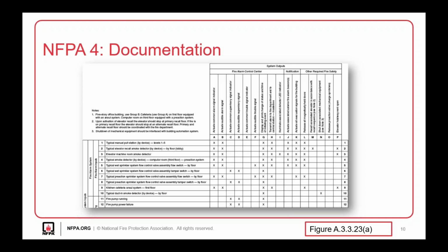So when performing the integrated test, it's important to document how each part of the input-output matrix was tested. This can be done in the form of a sequence of operation. The sequence of operation shows each input and then lists the subsequent outputs. And what it does is it allows the testing personnel to check whether each output is observed. So when you're documenting this procedure, it's also important to note how the input was created, whether or not it was an actual status change.